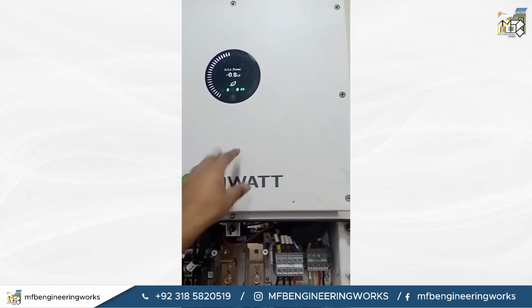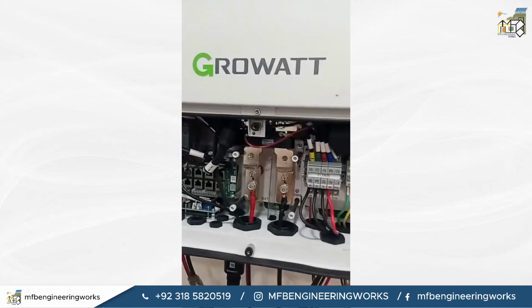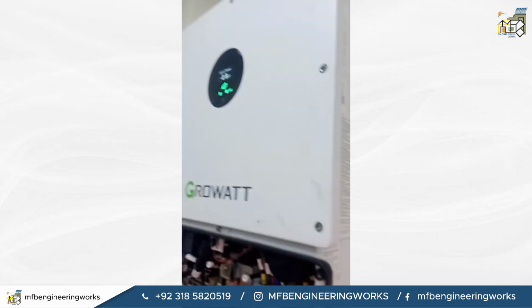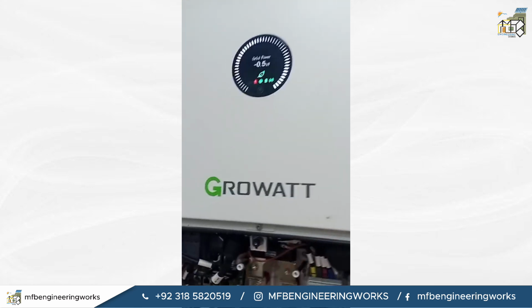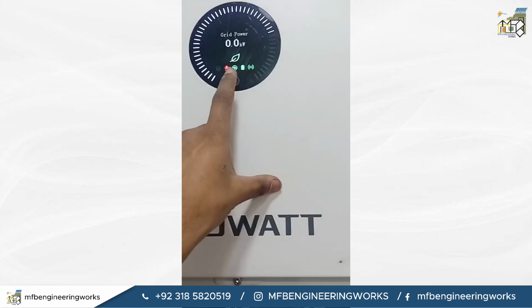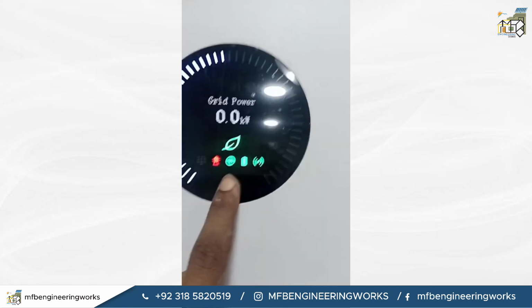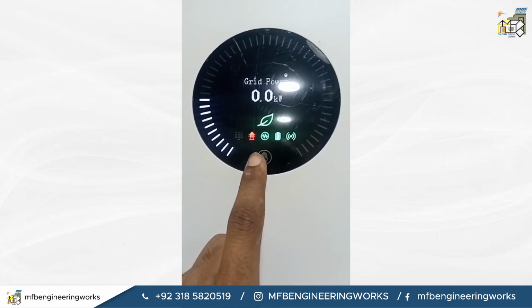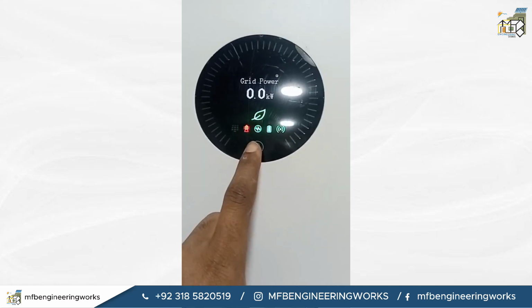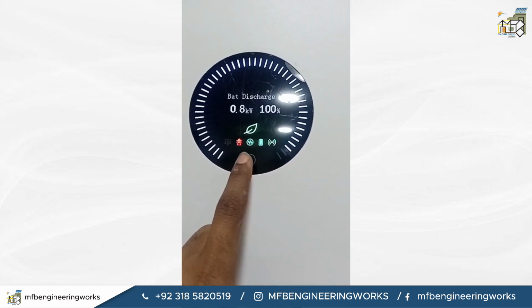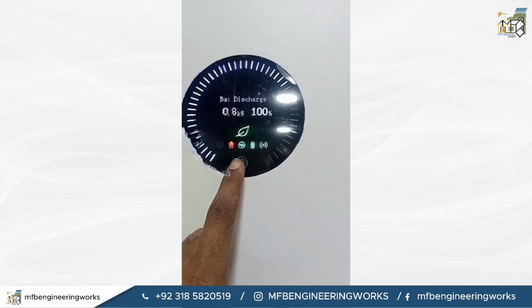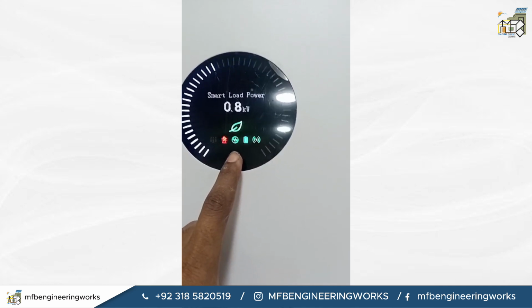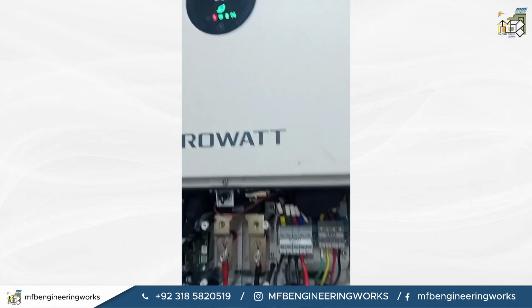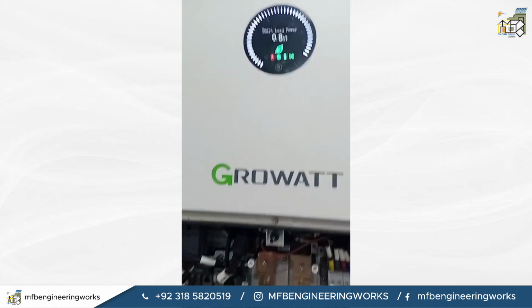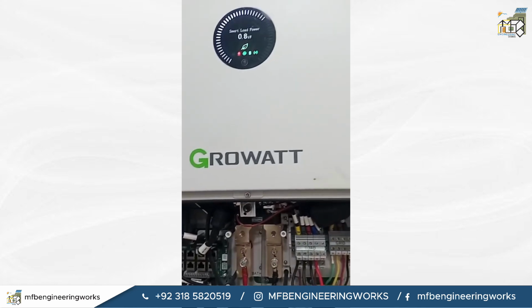Now we are going to disconnect the utility. After disconnecting the utility, as you can see, it has turned on the middle light, which means the system is now in off-grid mode and is running normally. As you can see, the battery is continuously discharging 0.8 kilowatt and the smart load is running at 0.8 kilowatt. The load is working normally and the system is properly working on all three sources. I have tested all three sources one by one.